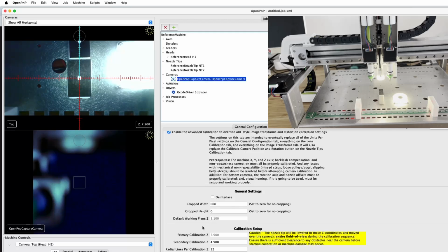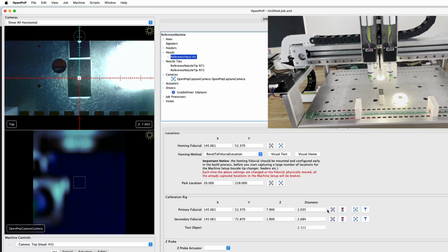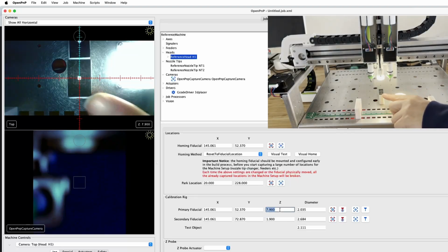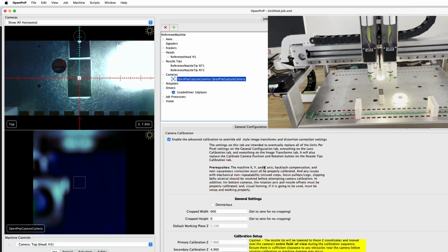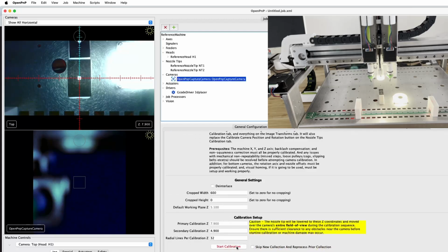And then the other one is basically primary calibration Z. So that has to be the same as this one, as here. So make sure it's at the same surface as the primary fiducial level. So this will be the main surface to work. And then here 4.9. So basically I just lower down like 3 millimeters for it to calibrate a second level. So it knows on different levels what the unit per pixel is. And then it can form a kind of 3D adaptation for different heights. Okay, so now we can do the calibration.